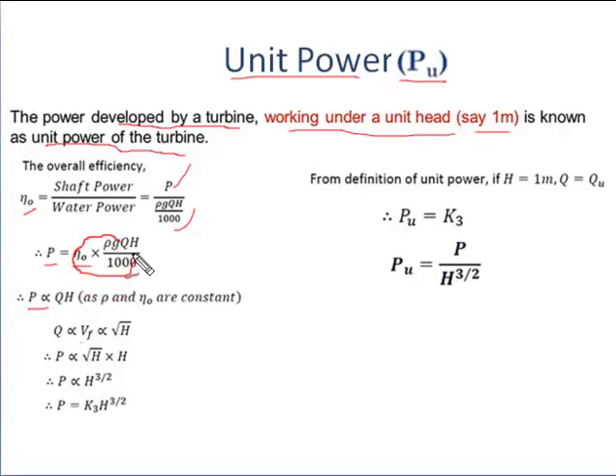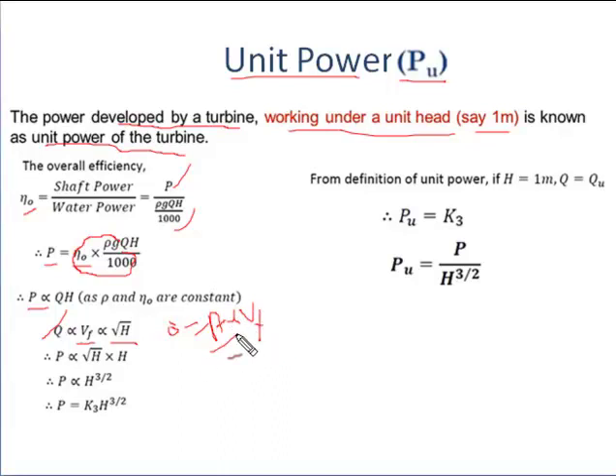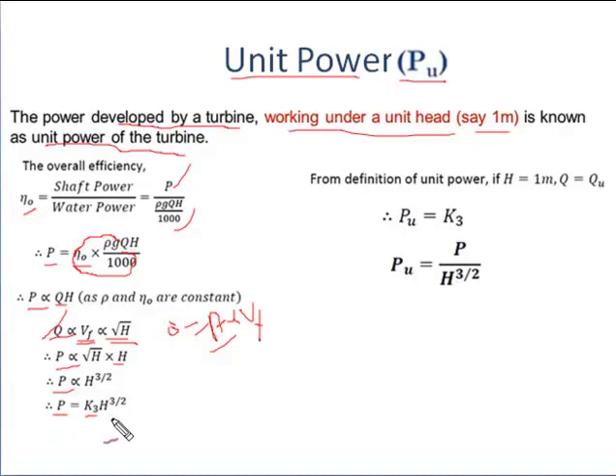Eliminating all constant parameters (ρg × overall efficiency / 1000), we get P is directly proportional to Q·H. Since Q is directly proportional to flow velocity, and flow velocity is directly proportional to √H, substituting gives P is directly proportional to √H × H. Therefore P is directly proportional to H^(3/2). Eliminating the proportionality constant, P = K₃·H^(3/2).